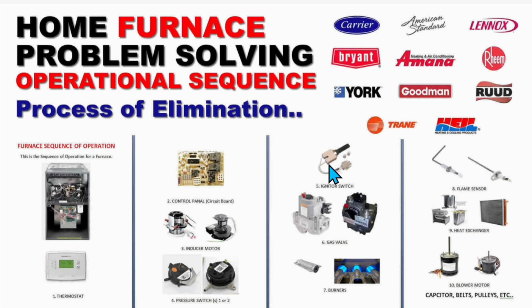If you don't get a glow, then you know that something's wrong with the igniter. You can take your meter out and check this and see what the readings are, or do that for any of these components. You will hear the gas valve click on and the gas start coming through. And then of course your burners should all light up. You may have 4 burners, 6 burners. They vary according to your model.